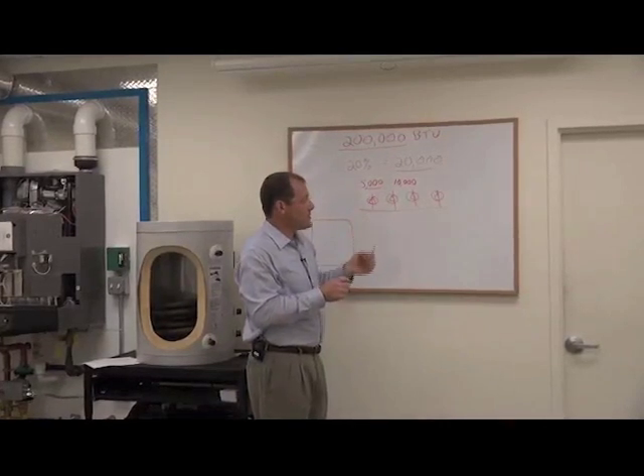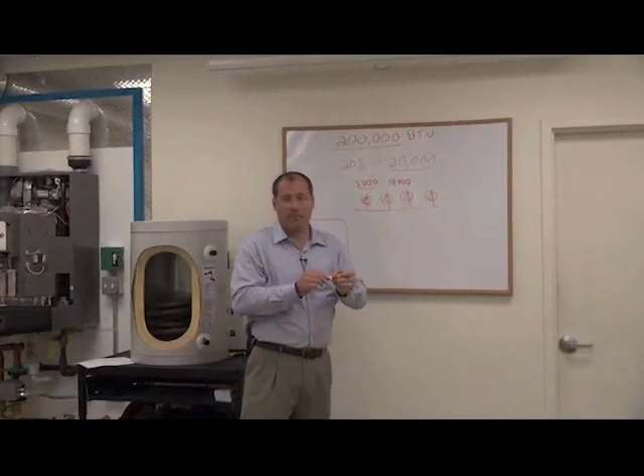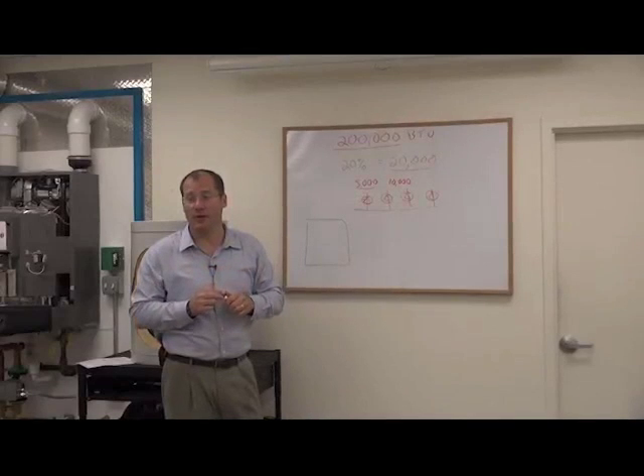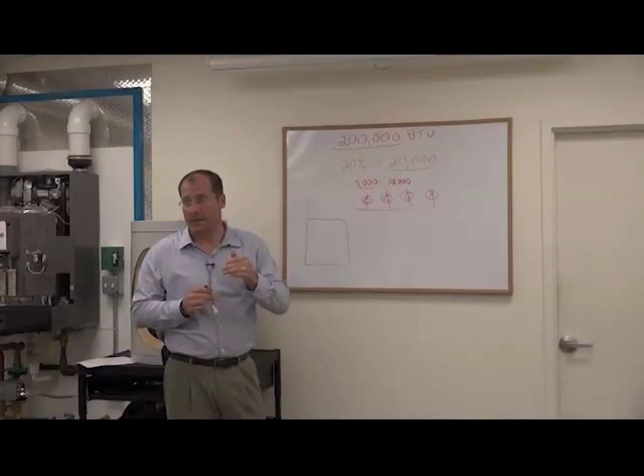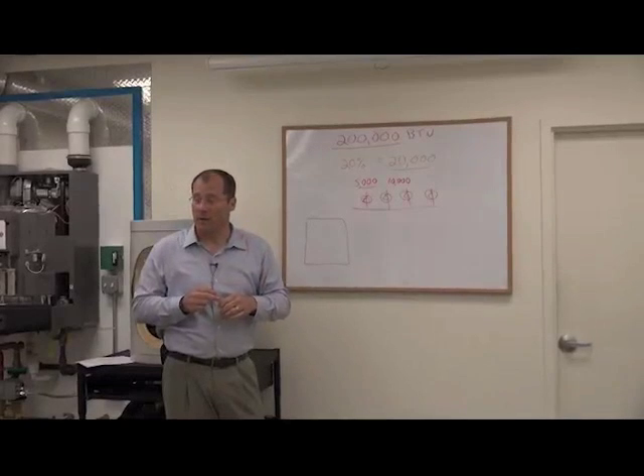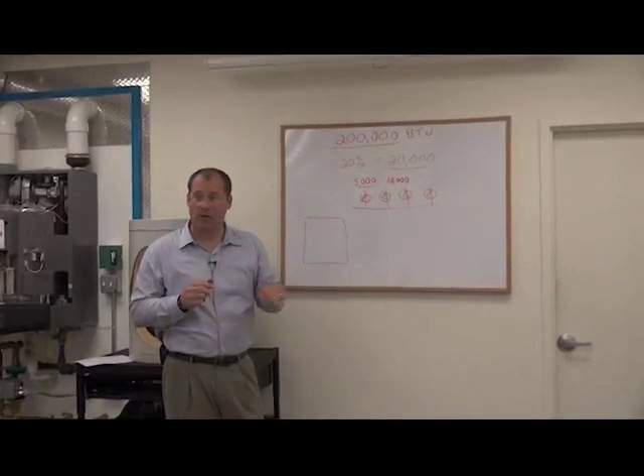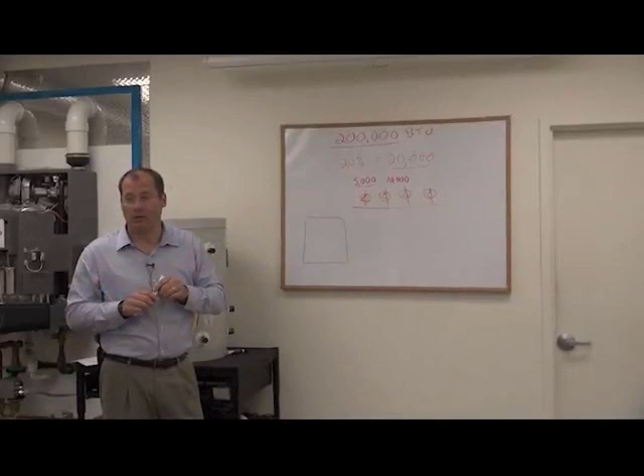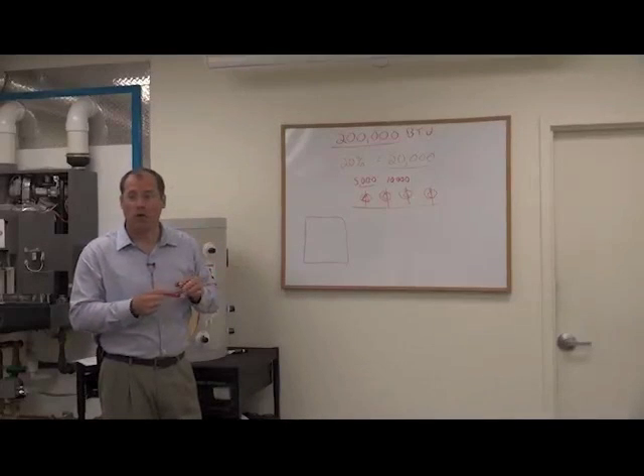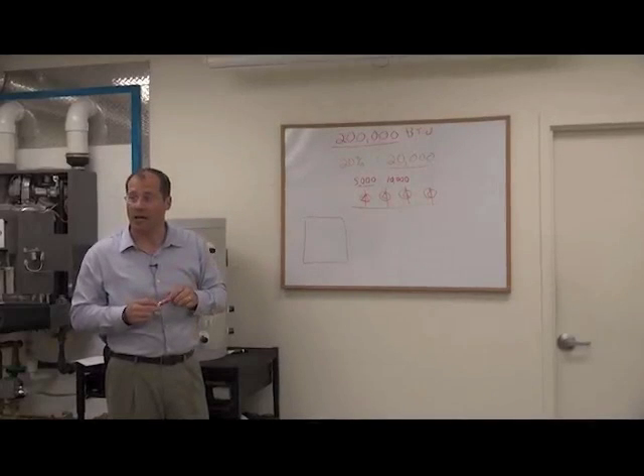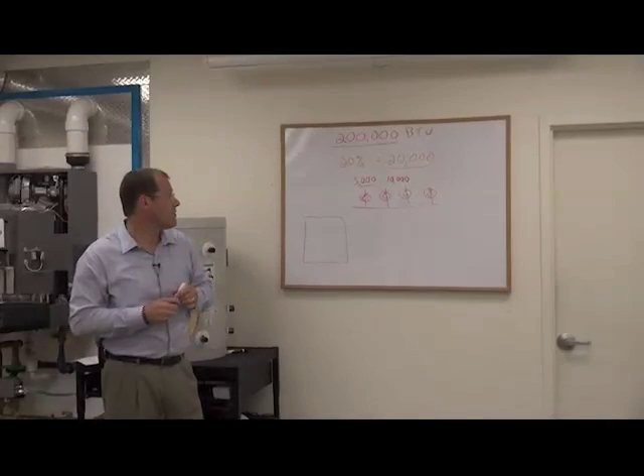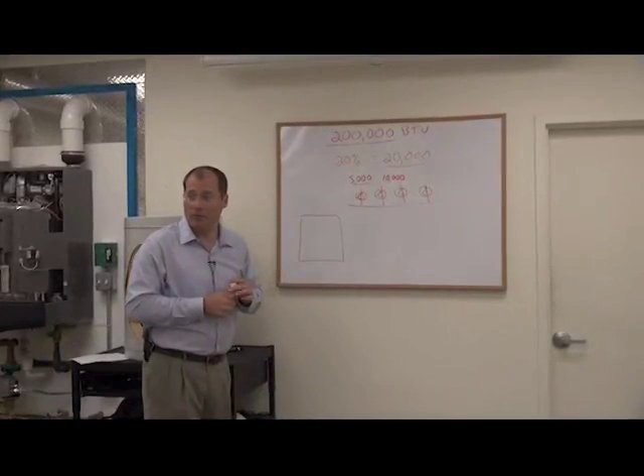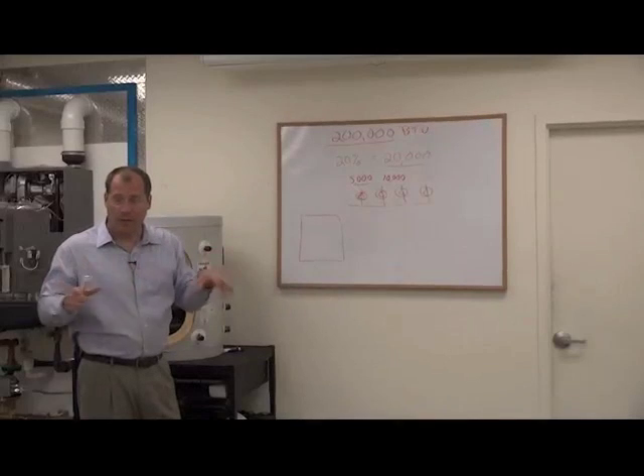So some contractors will use a rule of thumb. I'll use 40 BTUs per square foot. That's still a guess. And they say, well, I can add up all of the baseboard and all the radiators, and that's better because that's the connected load. You can determine how much heat could be put into the house, but it's still not the best way.